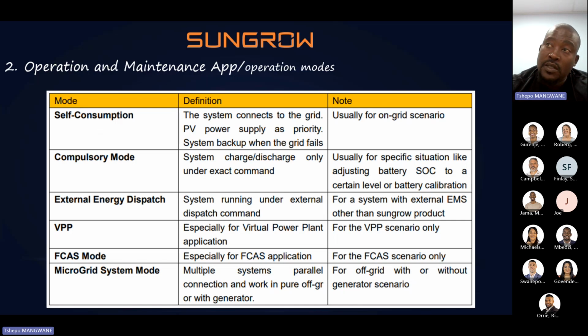We mainly set the system to self-consumption if the system has batteries, PV and grid as well. In this case, the system will use PV to charge the battery and supply the essential load. If the customer wants to feed back into the grid, we will open the system to feed back into the grid as well. The power can be redirected where it's needed the most. We can also set the reserve SOC on the battery side. If the customer wants to use 50% of the battery at night, then reserve 50% for load shedding or power cutoff. We set it on self-consumption, whereby we can set those settings: power cutoff, battery SOC level and so on.